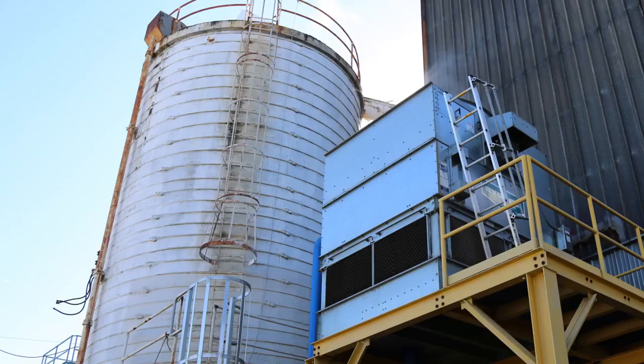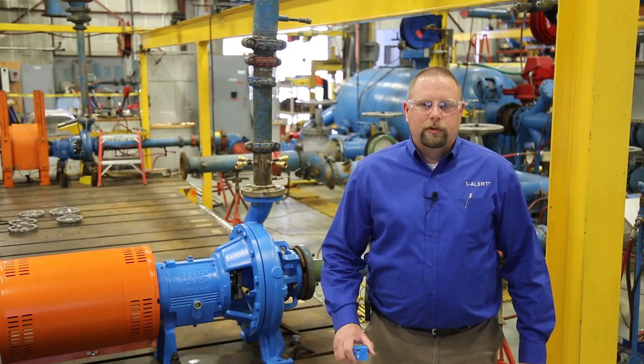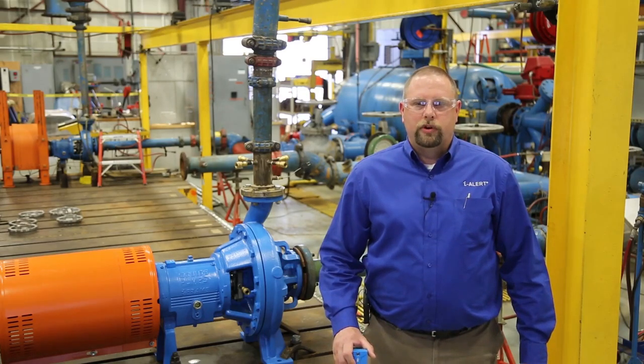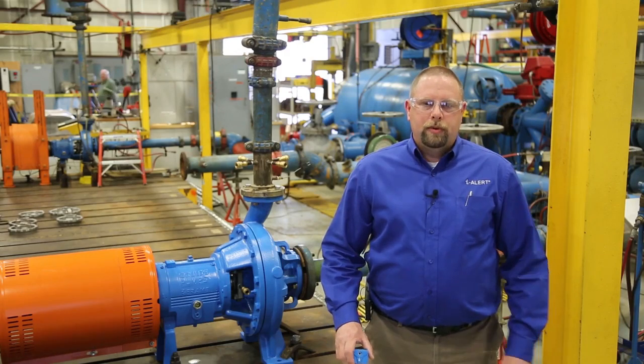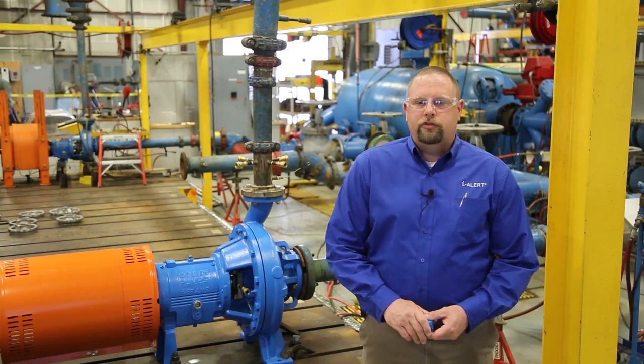One of our customers had an expensive failure of a motor in one of their cooling towers because no one could enter it to do vibration checks. While shutting it down during the repair, the gearbox and motors were fitted with iAlert sensors, and they never had another undetected failure.